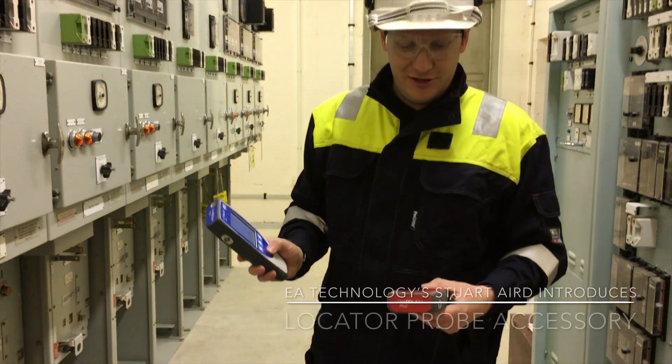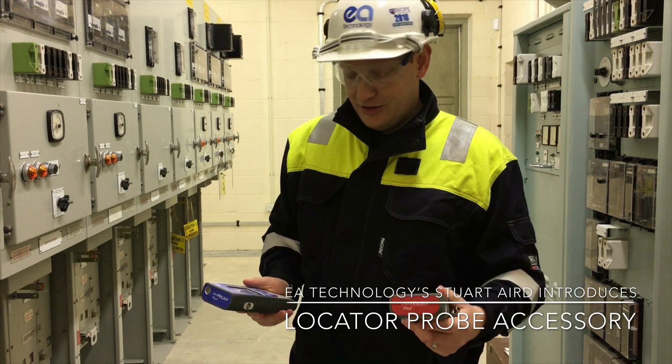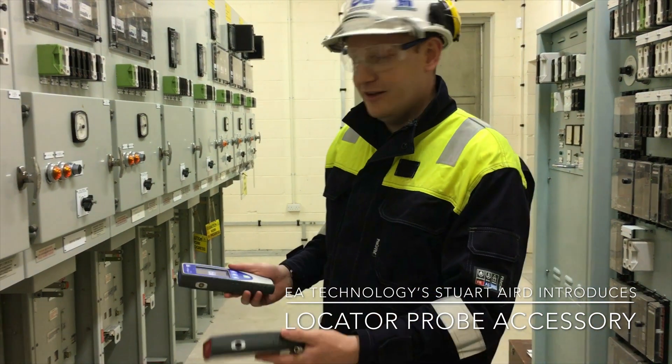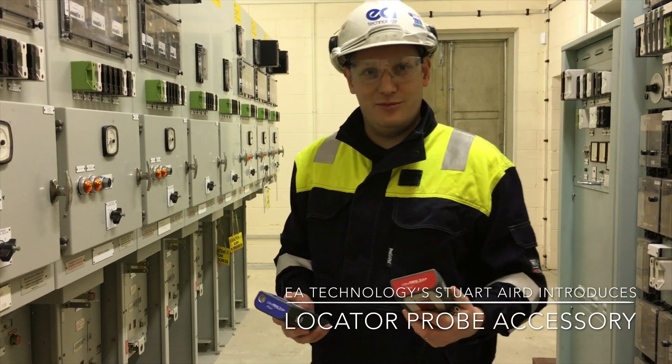We've got the UltraTEV Plus2 and the location accessory. Using this accessory we can locate TEV sources on our switchgear using the time-of-flight principle.